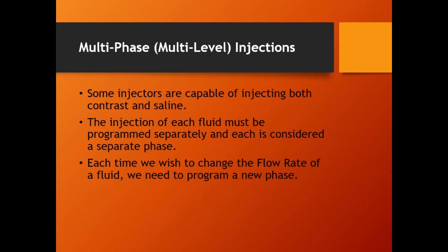The second phase is in blue, meaning it switches over to saline, with a flow rate of 5 and volume of 20. Then we go back to contrast for the third phase, with a different flow rate and volume. Then the 4th phase goes back to saline, again with a different flow rate and volume. So that is a multi-phase injection. Like I said, one model calls these levels, but they're called phases. So this is a 4-phase injection, but still just 1 injection.